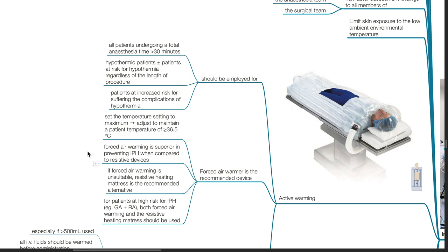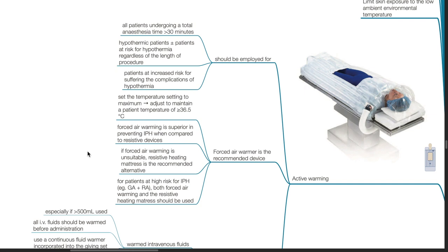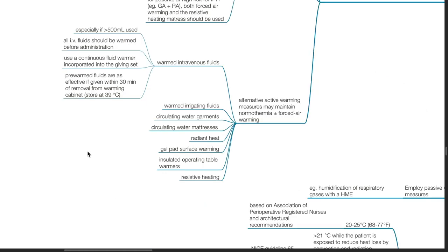Forced air warming is the recommended device. Set the temperature to maximum and adjust to maintain a patient temperature of 36.5 degrees Celsius or more. Forced air warming is superior in preventing inadvertent perioperative hypothermia compared to resistive devices. If forced air warming is unsuitable, a resistive heating mattress is the recommended alternative. For patients at high risk, both forced air warming and the resistive heating mattress should be used. Alternative active warming measures may maintain normothermia in addition to forced air warming, for example: warm intravenous fluids, warm irrigating fluids, circulating water garments, circulating water mattresses, radiant heat, gel pad surface warming, insulated operating table warmers, and resistive heating.